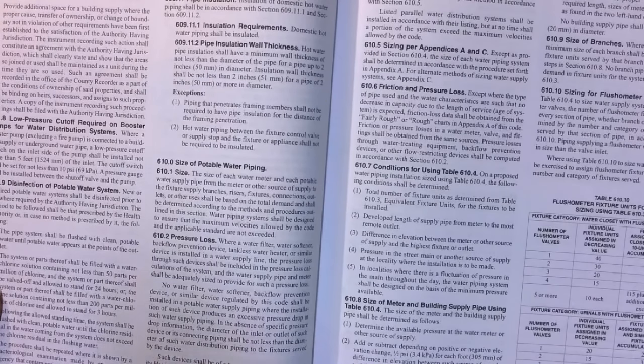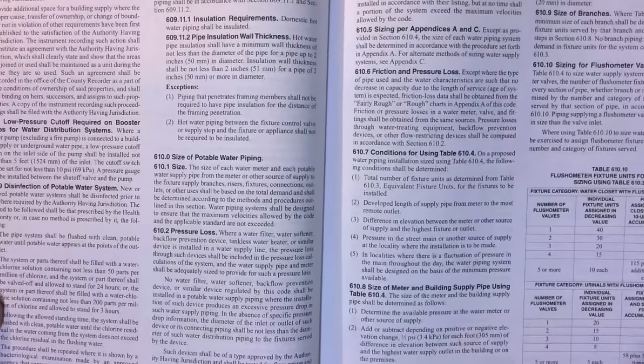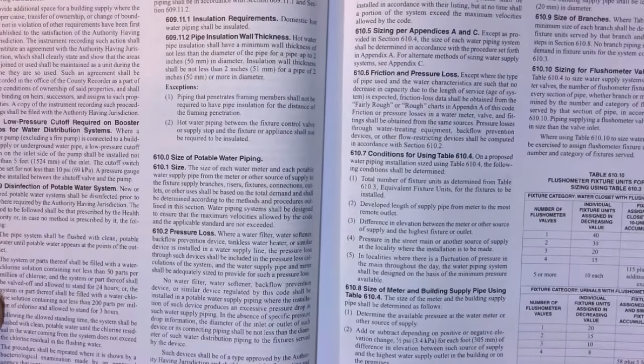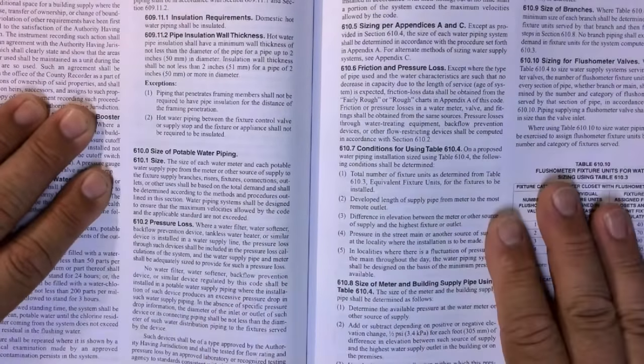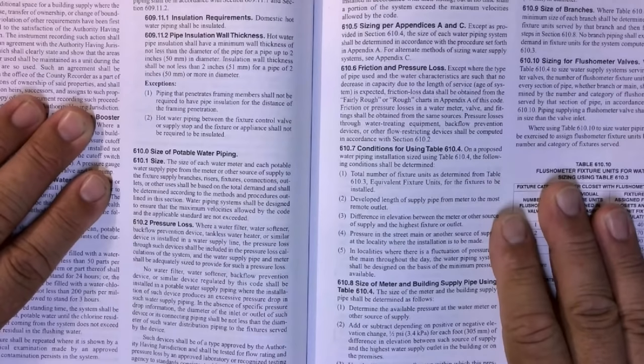Okay, sizing of a potable water pipe, or sizing of a potable water system. The size of each water meter and each potable water supply pipe from the meter or other source of supply to the fixture supply branches, risers, fixtures, connections, outlets, or other uses shall be based on the total demand and shall be determined according to the methods and procedures outlined in this section.